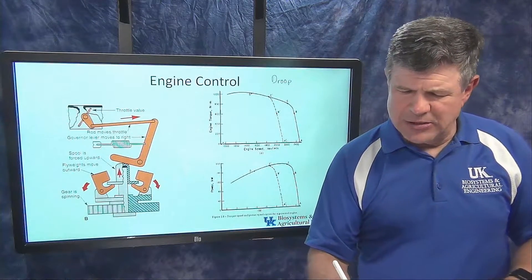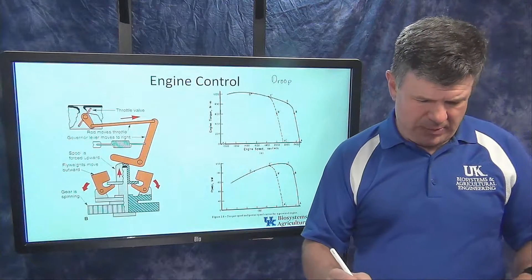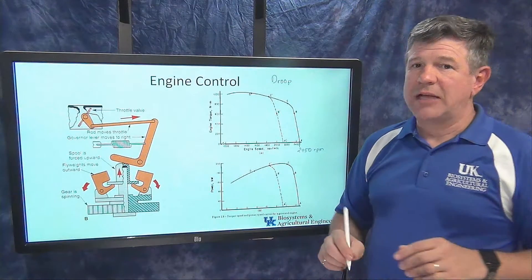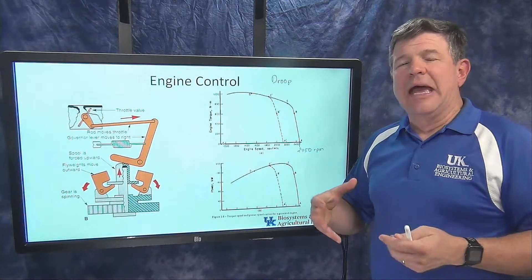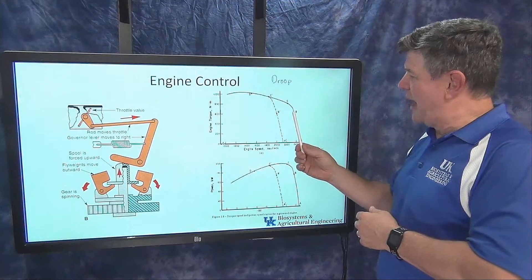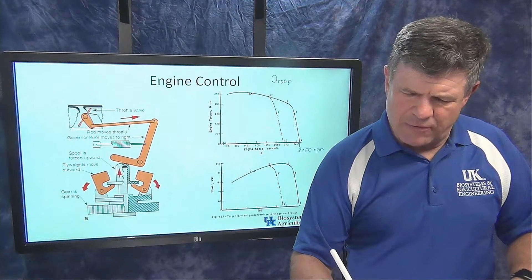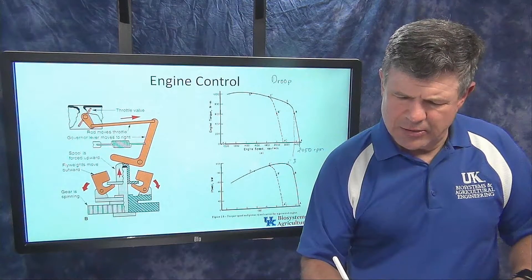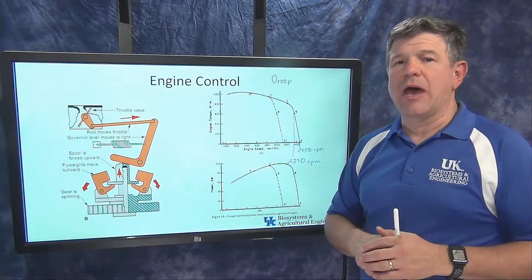Looking at this example on the graph — it's kind of small but — the wide open speed with no load looks to be about 2,450 RPM. Now if I put some load on it, the governor tries to respond and react. As I do that, the engine is still going to slow down a little bit. The governor works hard to control that speed, but there will be some speed variation. Going back to the shoulder point, labeled B on the graph, where the governor stops, and drawing a vertical line down, I'm estimating that speed to be about 2,390 RPM.